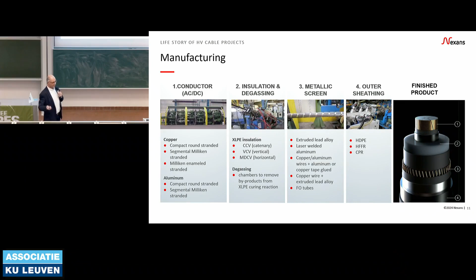The cable is done, you have to test it. The story is not yet ended in your project. The time is still running. You still have to make sure the cable is 100% sure. In the cable industry, each drum, each centimeter of cable is tested. We are not making random testing, we are making 100% testing on all accessories and all cables. Why? Because if we don't do so, and we have a breakdown, it will cost 10 times more than what we produced. So it's very important to test all this.